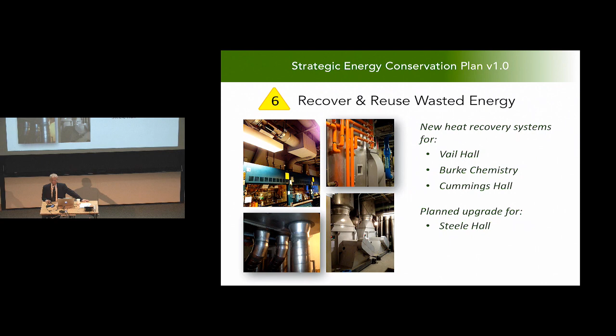If we take strategy 5 and 6, the chiller replacement and the heat recovery, and put those together, we can show you a great example - the Burke Chemistry project, where we replaced 2 very large absorption chillers with electric chillers and replaced all the airflow controls, and added heat recovery to the building for the first time. The overall results were a 64% reduction in energy use for the building, which previously was the top energy-using building on campus. It has now slipped down, luckily, to number 2, and it's headed lower to maybe 3 or 4.